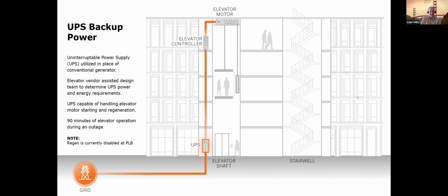But yeah, so here's a quick diagram of our system. UPS is fundamentally powered by a grid under almost all cases. The building does also have a microgrid system, so if we lose the grid, we have the ability to provide full backup to the entire facility. But that backup from the microgrid, not shown here, is not code compliant for emergency power. So we had to have a dedicated appliance, and that is the UPS.